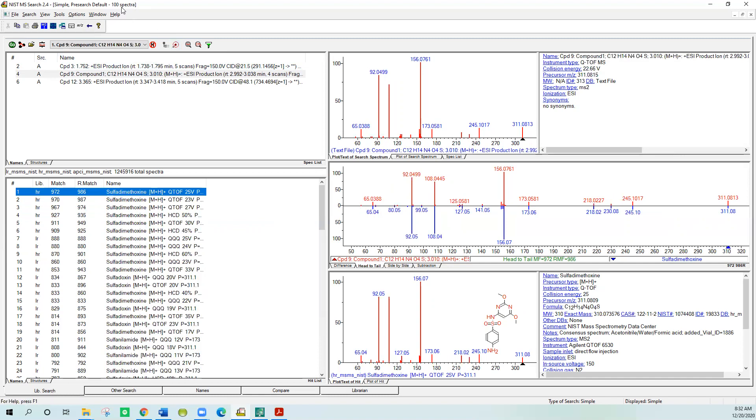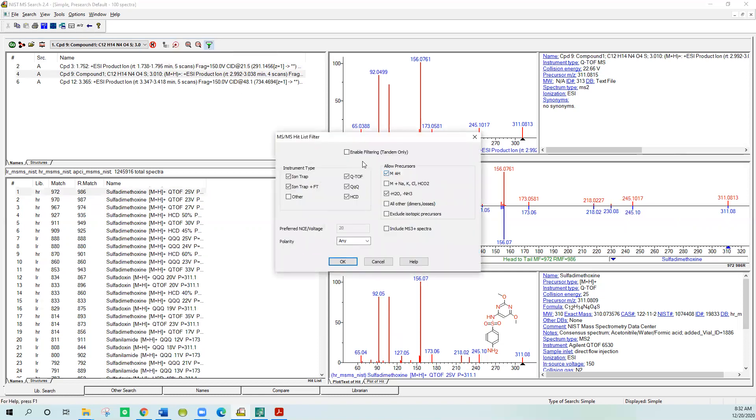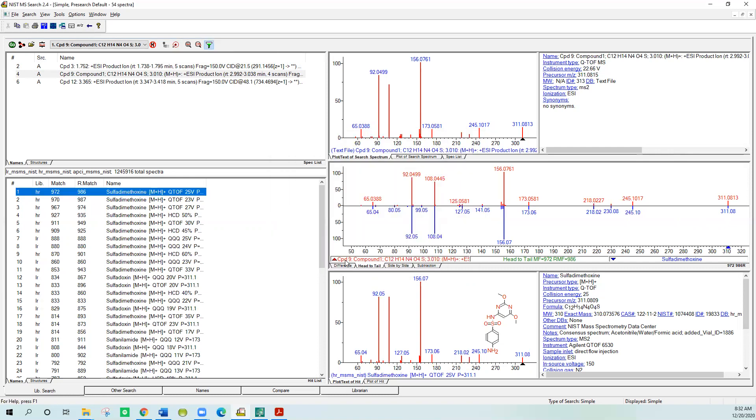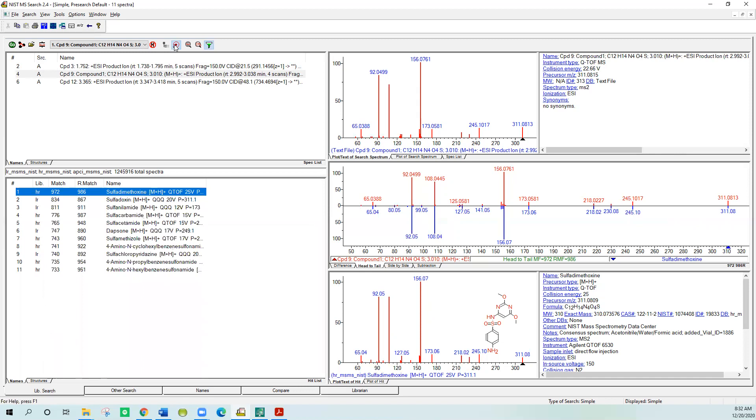There's one other way you can filter things up here. Let's turn the target back off to open it up, so we go back to our 100 spectra. This thing that looks like a filter funnel, this searches by a lot of different things. You can enable filtering here and select different parameters that you want to eliminate these types of things from the hit list, from the things from the library. So let's enable the filtering here with the ones that are selected right now and see what happens to our number. Remember we started with 100 up there. So we say okay, and it's dropped to 54 spectra.